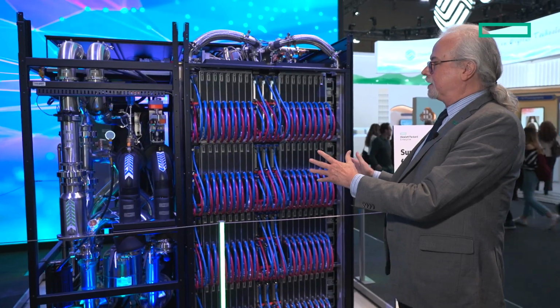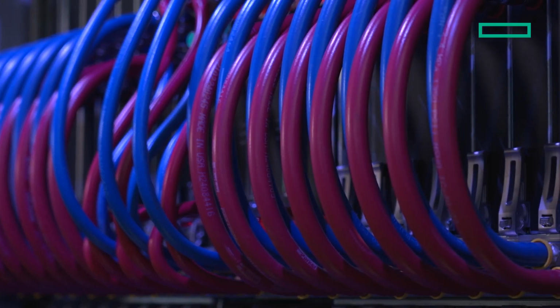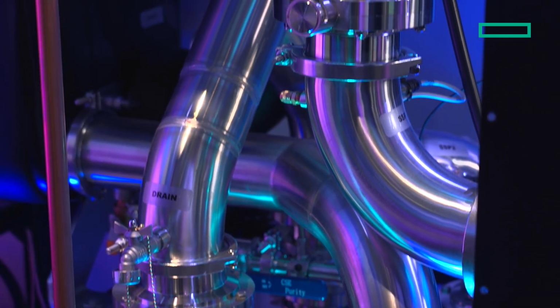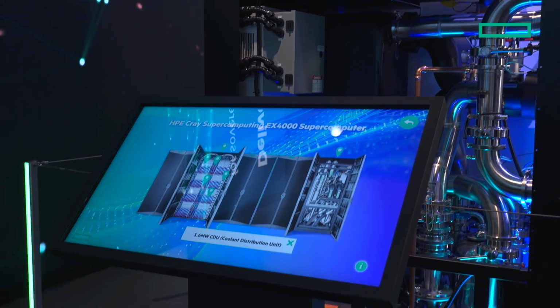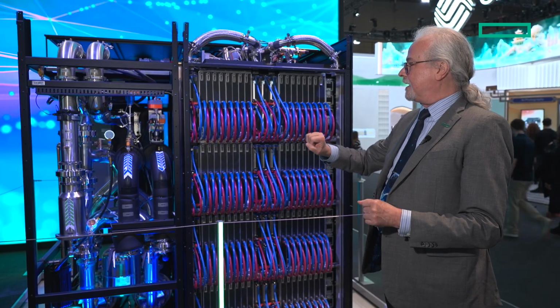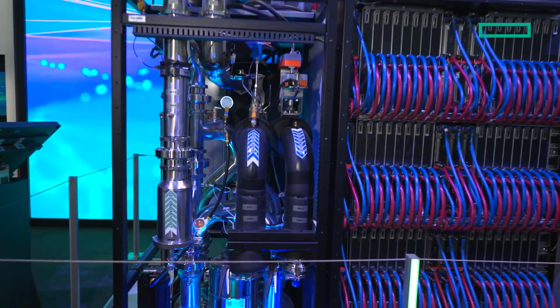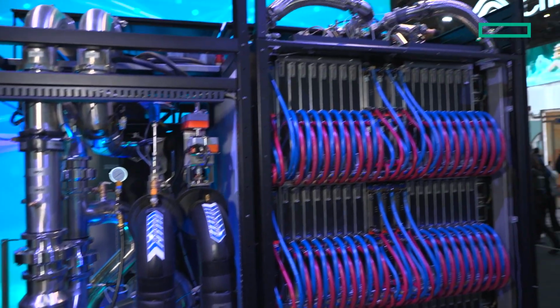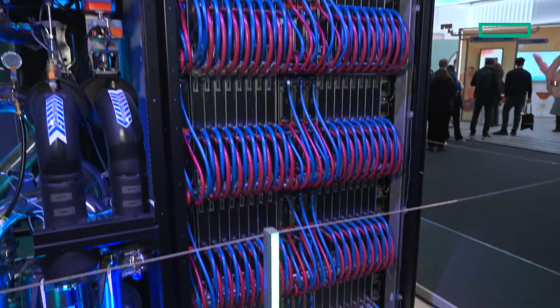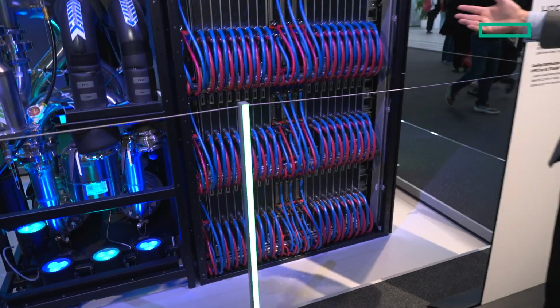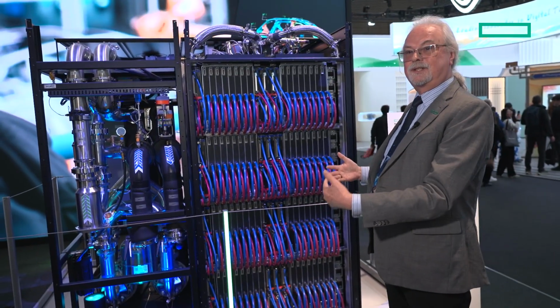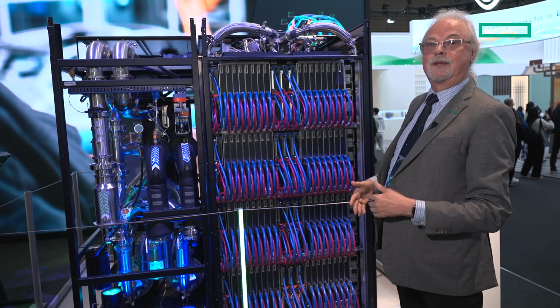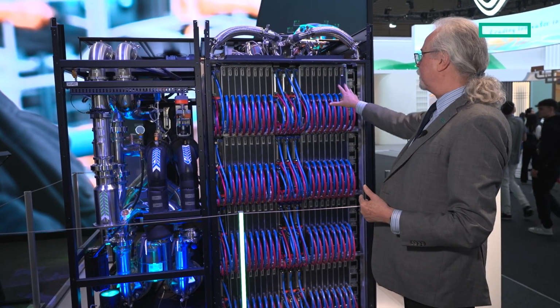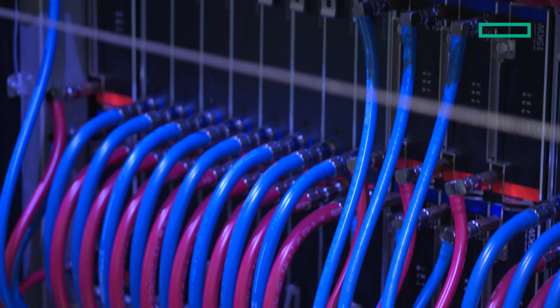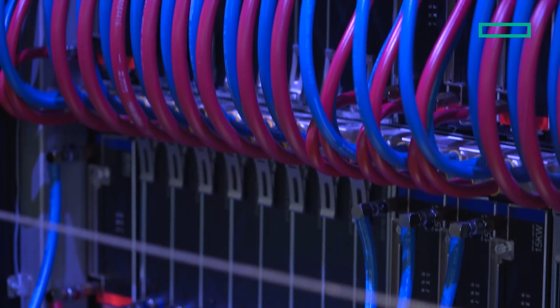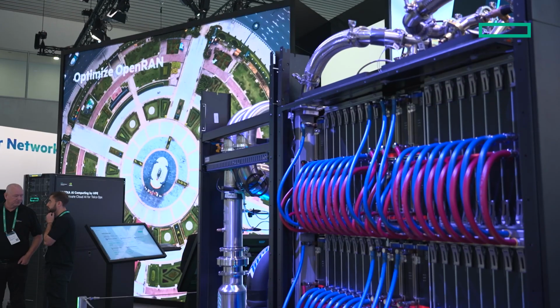So what we're showing here is part of a supercomputer straight off of the manufacturing line. This is only a small part of the entire supercomputer. We see here on the left side a distribution rack for the liquid cooling that then goes over the top to all of the compute racks. We can have, in a situation like this, up to 4 compute racks, and then, depending on the customer's needs, 5, 10, 20, 30 of those rows of compute racks. Each compute rack consists of 8 modules with 8 servers, so 64 servers in one cabinet.